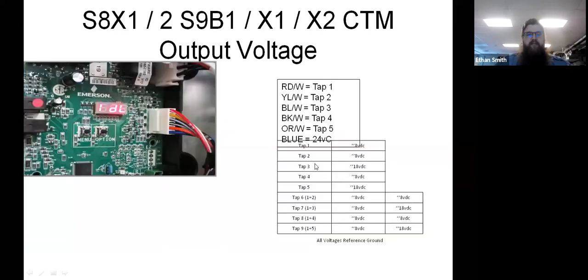Well, programmers are sneaky little bastards. And what they figured out is they could actually take this motor and instead of sending it 24 volts all the time, you could send it a DC voltage. And so we can send this thing a DC voltage to tap 1, 2, and 3, 4, and 5 and get 5 speeds. And then we can take it and actually send it DC voltage on multiple taps and get more speeds. So tap 1 through 5 is speeds 1 through 5.